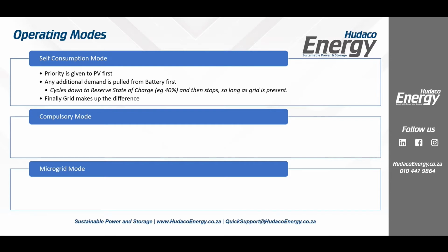So in other words, you may say, well, why am I running my non-essential loads from battery? Well, because at a Rand 66 or whatever the price ends up being, it's cheaper than bringing in new energy at 2 Rand 68, especially considering that later on that day or tomorrow morning, the sun's going to come up again and recharge our batteries for us. That reserve state of charge is a limit that we can manually set to say, do not go below this limit in self-consumption unless my grid falls away. In other words, unless I have a grid failure and or load shedding. You know, the inverter doesn't distinguish between the two. The moment that happens, that reserve state of charge falls away, it recognizes the grid is gone, and it'll start moving down. Sean, I'll come back to your question a little bit later. Thank you, I have seen it. And then finally, grid makes up the difference.